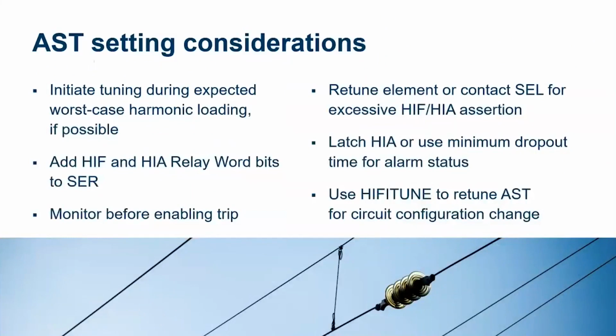We definitely do not recommend just going out there, turning on the element, and putting your HIF fault bits into your trip equation. We recommend setting up the system, going through the initial tuning, and then watching it, seeing what happens.